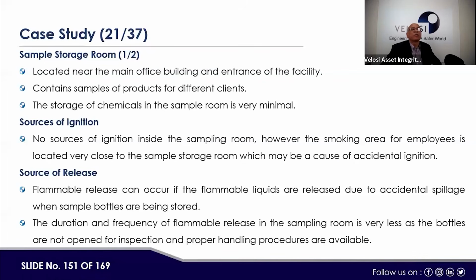Then the sample storage room, which is located near the main office building and entrance of the facility. Containers contain samples of the product for different clients. The storage of chemicals in the sample room is very minimal. Source of ignition: no source of ignition inside the sampling room. However, the smoking area for employees is located very close to the sample storage area, which may be a cause of accidental ignition. Source of release: a flammable release can occur if the flammable liquid is released due to accidental spillage when sample bottles are being stored.